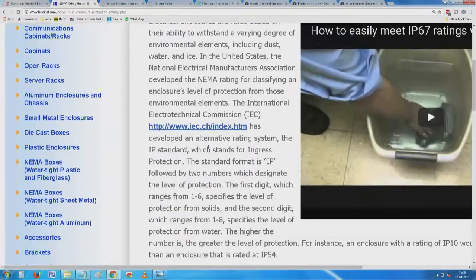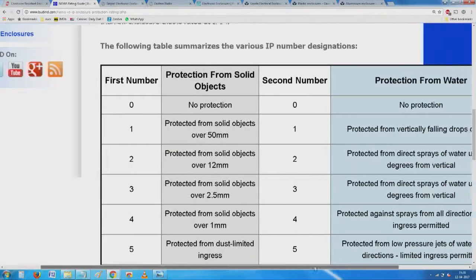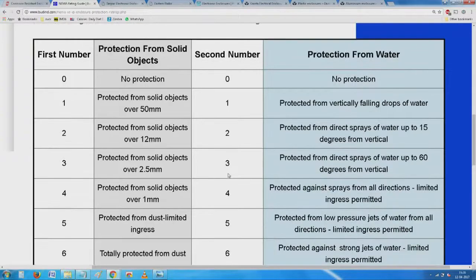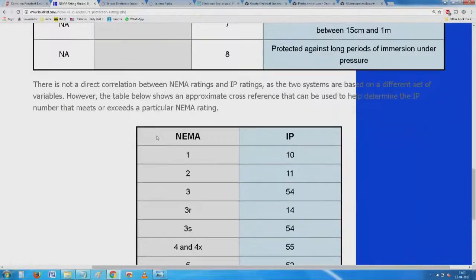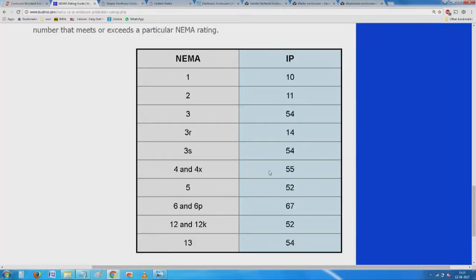I suggest you visit their website to find out about IP number designations. The smallest rating covers open chassis equipment — for example, a power supply mounted in a panel where the outer enclosure is fully protected. IP20 and IP10 mean a box that is generally protected but expected to be used inside another enclosure. Most small subassemblies, including PCBs, fall in this category.